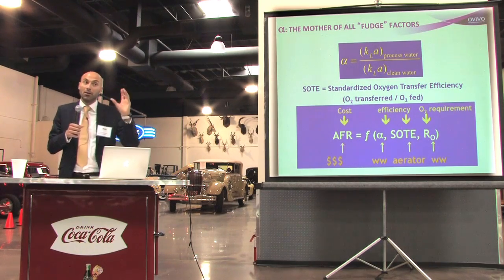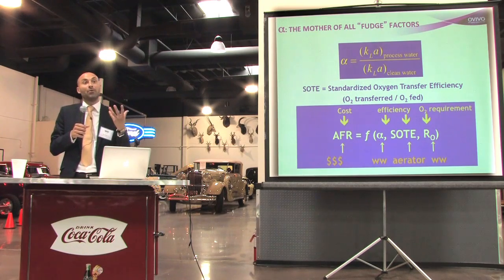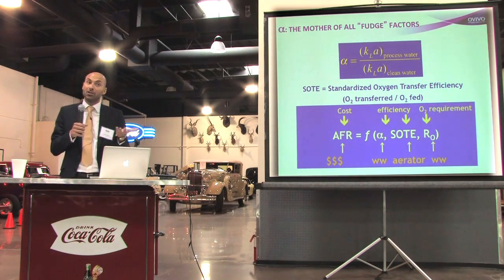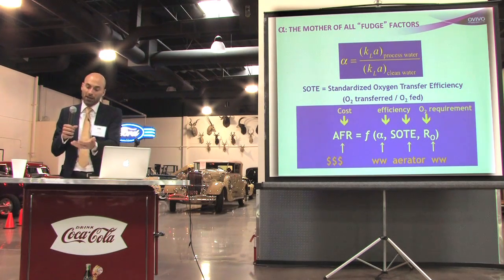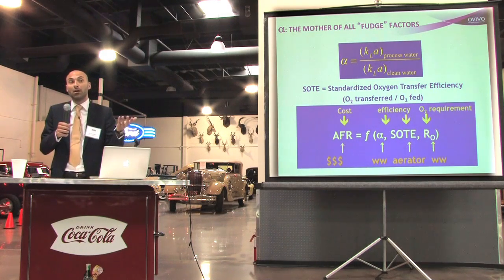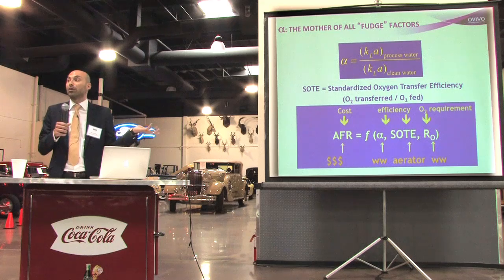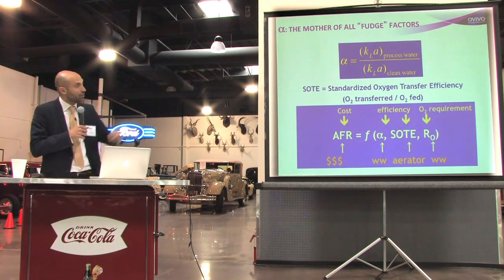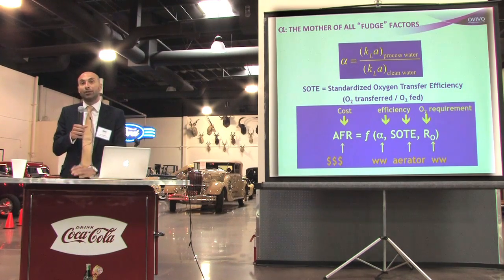The type of aerator, diffuser technology, and floor geometry dictate the SOTE. SOTE is strongly affected by diffuser density — one strip or one disc versus many in the same area. This is a capital investment tradeoff: more diffusers for better efficiency and lower operating costs, versus fewer diffusers for capital savings but higher long-term operating costs. The oxygen requirement is the flow rate times the load, which changes every hour of the day.